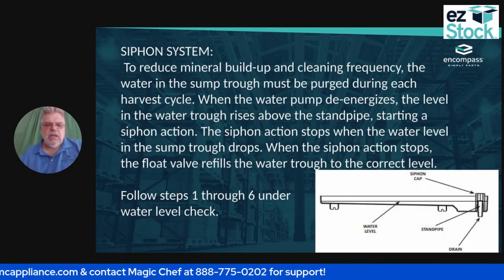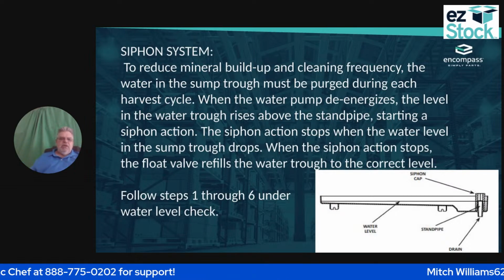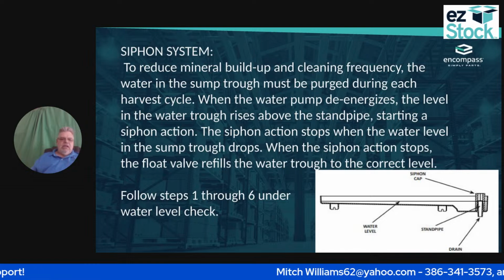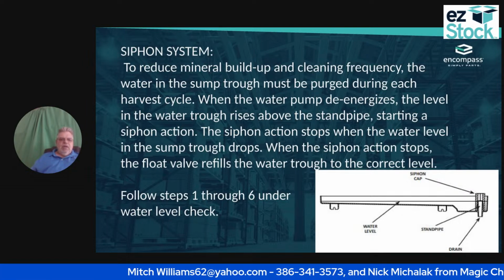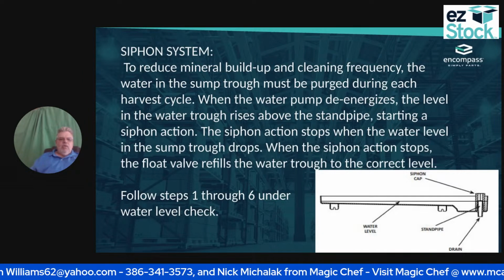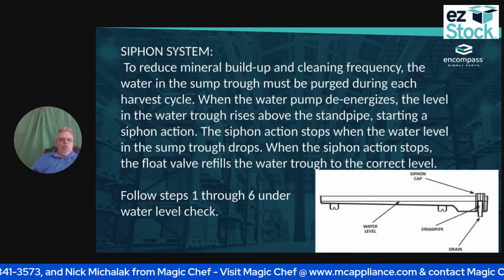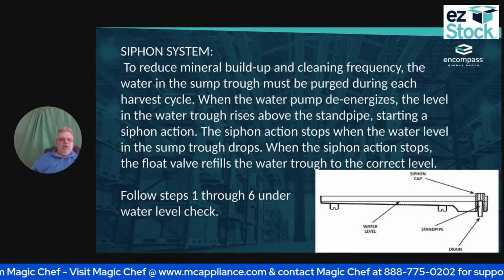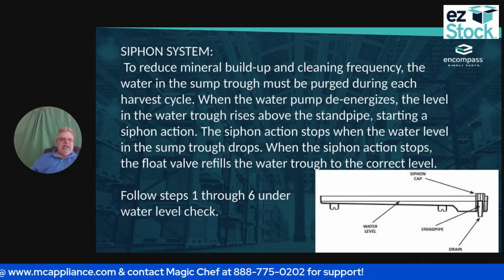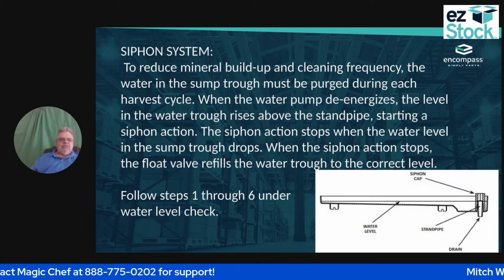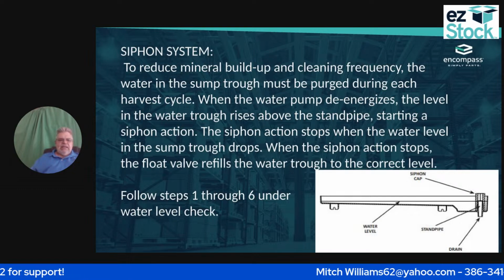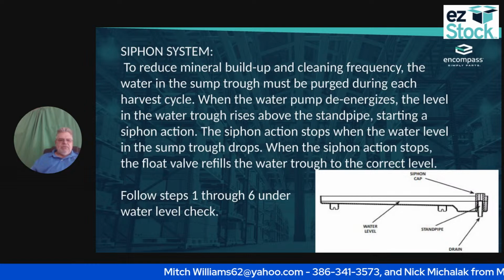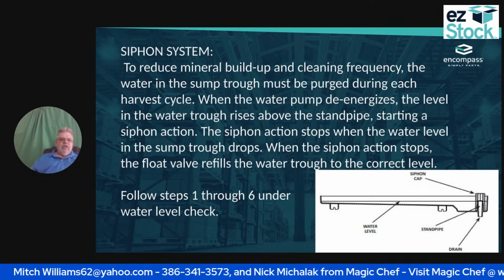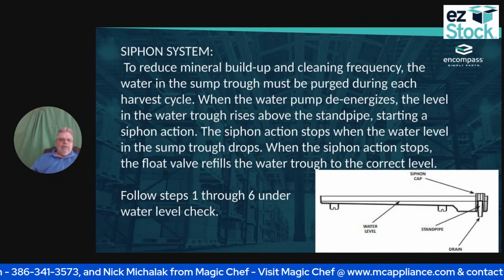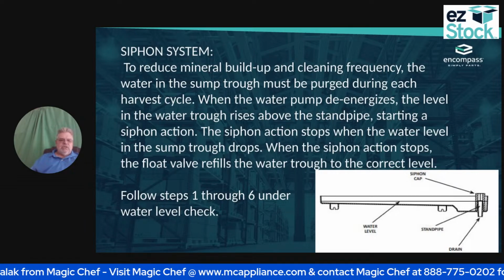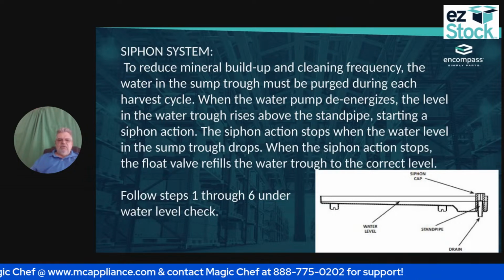So let's talk about the siphon system. To reduce mineral buildup and cleaning frequency, the water in the sump trough must be purged during each harvest cycle. When the water pump de-energizes, the level of the water trough rises above the standpipe, starting a siphoning action. The siphoning action stops when the water level in the sump drops back down below that. When the siphon action stops, a float valve refills the water trough to the correct level. So I'm going to follow the next 1 through 6 checks for the water level.